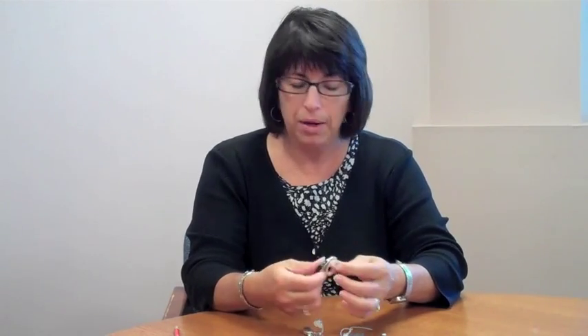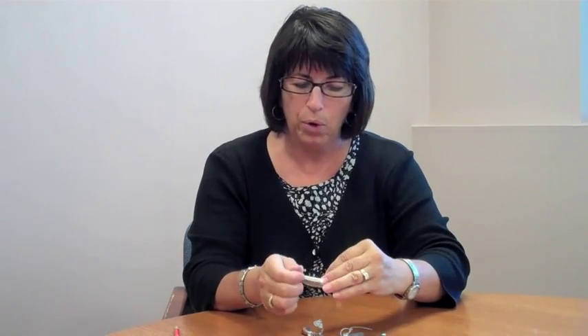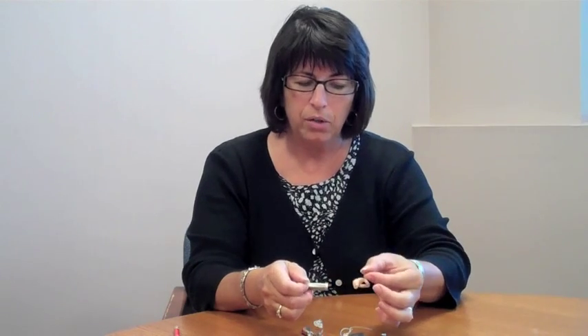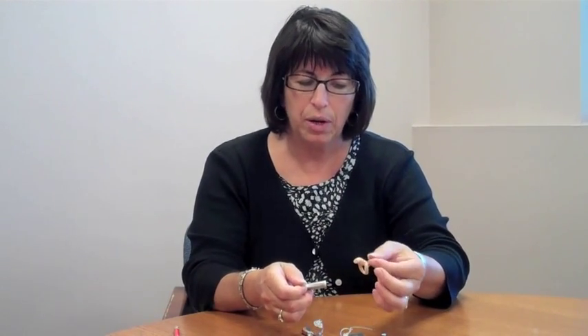The hearing aid could also not be in the correct program, so you want to check the other programs to see if you are in the correct one. Also, you would want to double check for moisture in the tubing. On a behind-the-ear hearing aid of this sort, it's usually rather evident that there's moisture in there, and you can get rid of it by pulling the hearing aid apart from the mold and using a recommended blower to remove that moisture. You don't ever want to blow into it to try to remove that moisture. You'll just create more moisture in there. With an in-the-ear style, there's not really an easy way to check for moisture. You're best off just putting it in the dryer and seeing if that takes care of the problem.